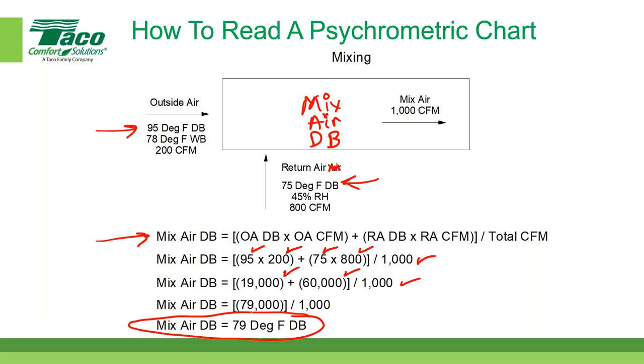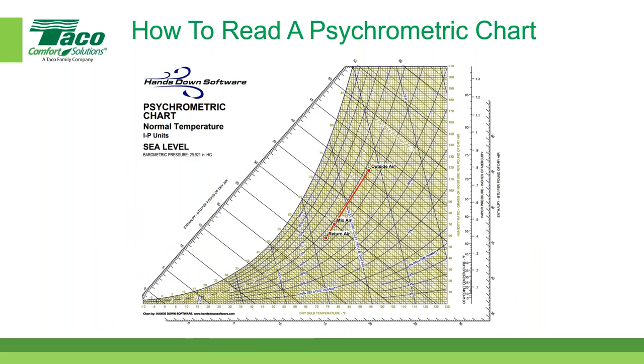When we plot it on a psychrometric chart, it looks like this. The outside air is right here. The return air is right here. If I connect those two points with a straight line, and then I take the new mix air dry bulb temperature, which we said was 79 down here somewhere, and draw a vertical line, it will intersect this diagonal line at the mix air point. So I manually calculated the mix air temperature, depending on what kind of software you have, and then I plotted it on the psychrometric chart.